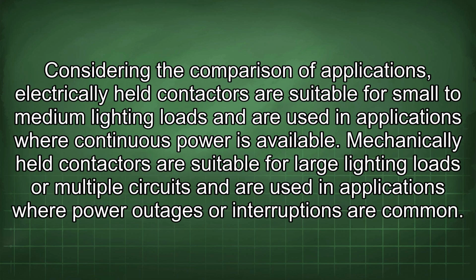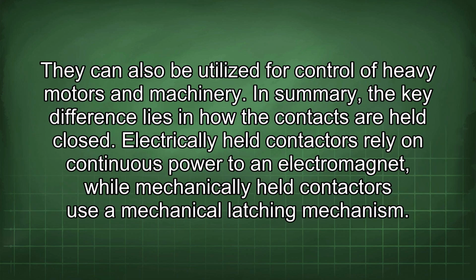Considering the comparison of applications, electrically held contactors are suitable for small to medium lighting loads and are used in applications where continuous power is available. Mechanically held contactors are suitable for large lighting loads or multiple circuits and are used in applications where power outages or interruptions are common. They can also be utilized for control of heavy motors and machinery.